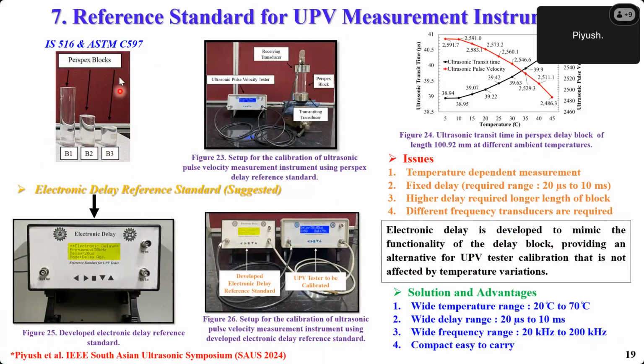So in this slide I'm going to present this reference standard. According to IS 516 and ASTM C597, both instruments need to be calibrated with the help of this calibration block. These calibration blocks have some issues, like the ultrasonic pulse velocity changes in these blocks with temperature. As we can see from figure 24, with the increase in temperature, the ultrasonic pulse velocity decreases. So this is a very big error in the measurement.